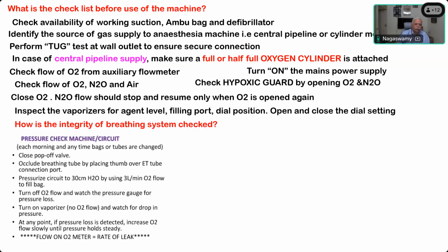We need to check the pressure, check the machine each morning and any time bags or tubes are changed. Close the pop-off valve first and foremost, or the APL valve, whatever valve is there, close it. Occlude the breathing tube by placing the thumb or the palm over the ET tube connection port. That is the Y port that is there. To close it with your thumb or with your palm. Pressurize the circuit to 30 centimeters of water by using 3 liters of oxygen flow to fill the reservoir bag.